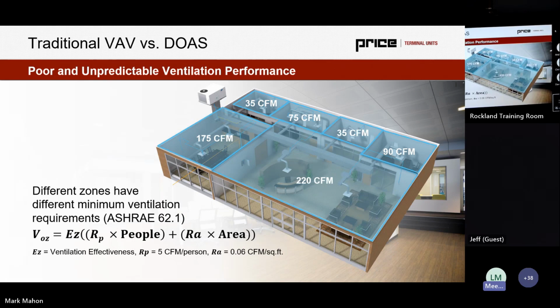In this case as well, assuming mixed overhead air distribution in cooling, our ventilation effectiveness is 1. So that means we're as effectively getting air into the breathing zone as we are into the return. It means we're not seeing too much stratification. It means we're mixing the space effectively so we have the same pollutant concentration throughout the breathing zone.